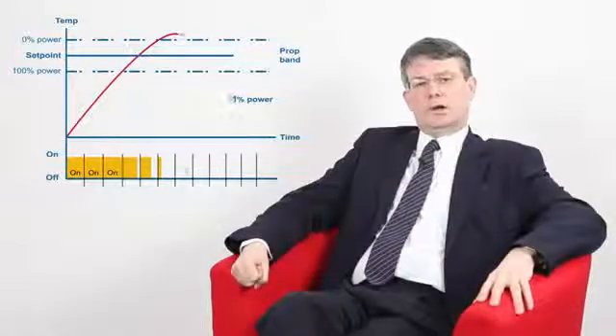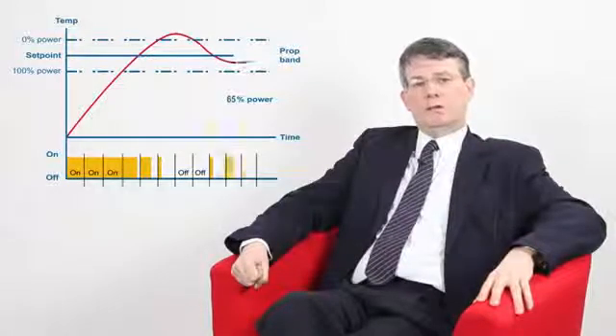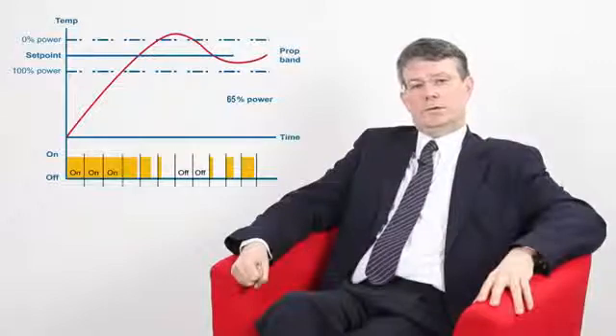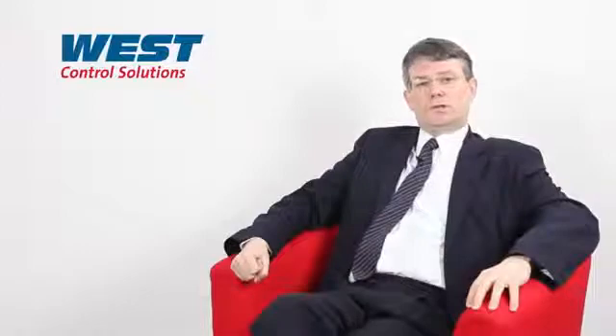If the user set a cycle time of eight seconds and the output was on for two and off for six, this would equate to 25% of power. Similarly, if the cycle time was set to 64 seconds and it was on for 16 and off for 48, this would also be 25% of power. However, the number of switching cycles would be reduced considerably, so you can see how the user can control how often their devices are switched.